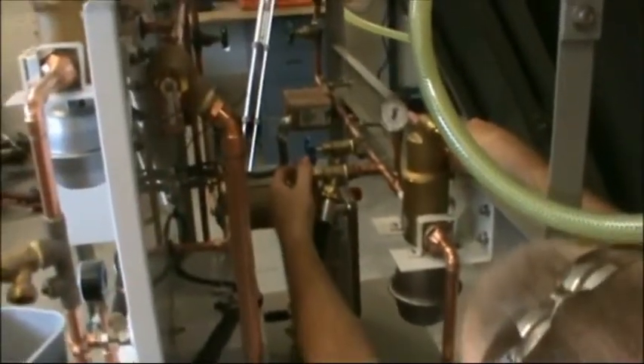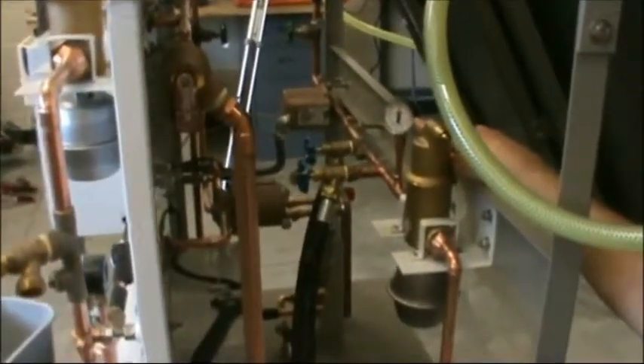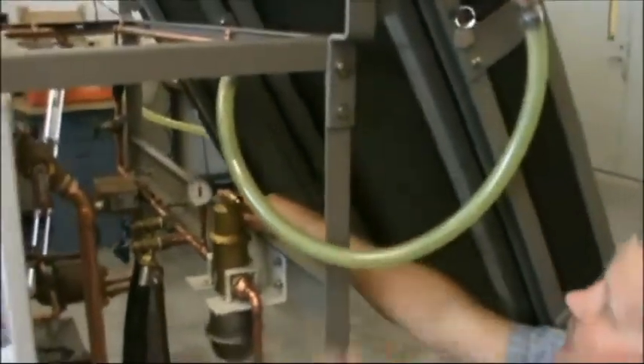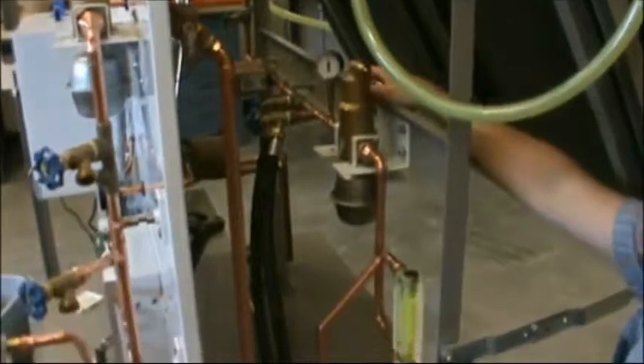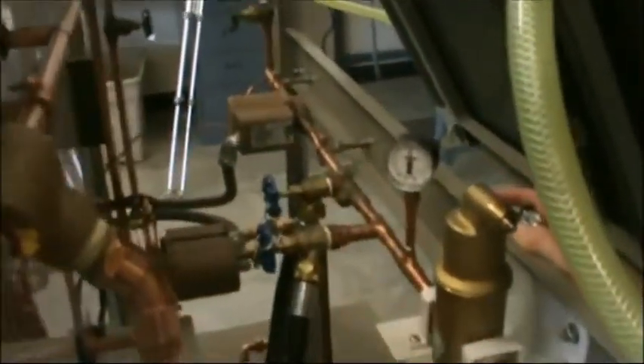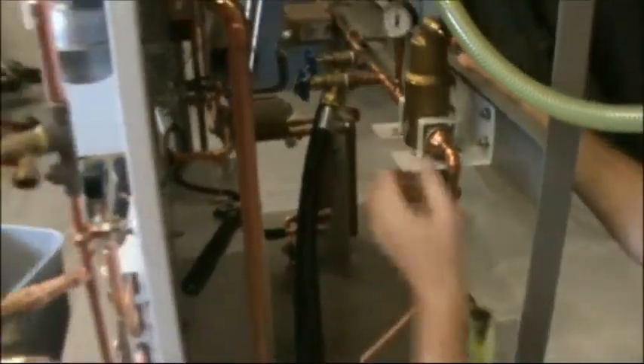I'll open this valve as much as I can. Now they say not to exceed 15, so I'll back down to 15 psi. So I have full flow that this system can handle at 15 psi. It's coming in, I shut that valve in the middle so only the fluid comes in, comes through the valve, through the system, through all the pumps, the heat exchanger, and back into the inlet.